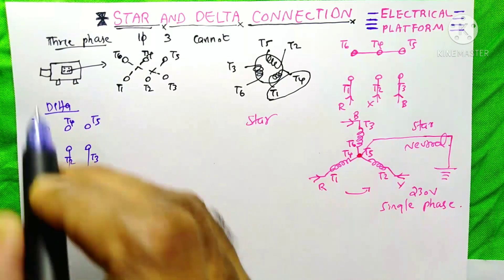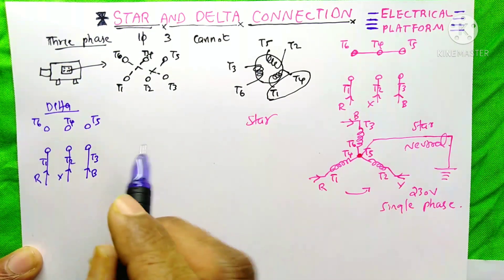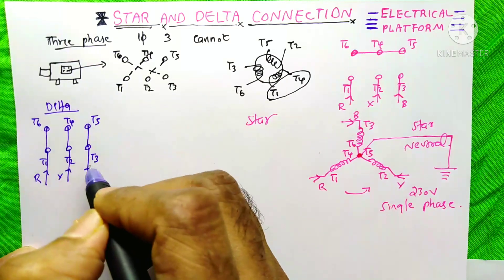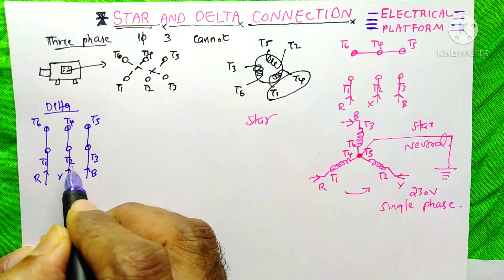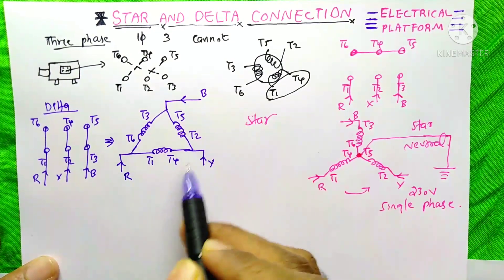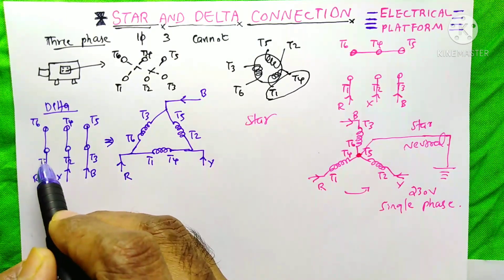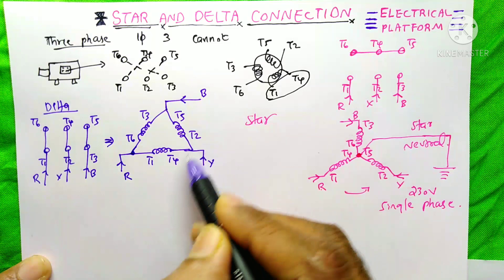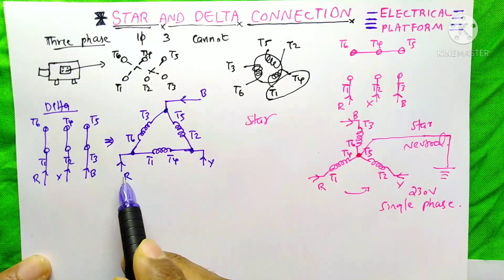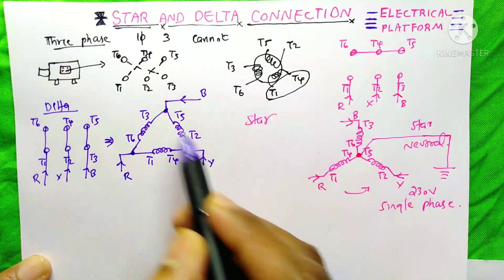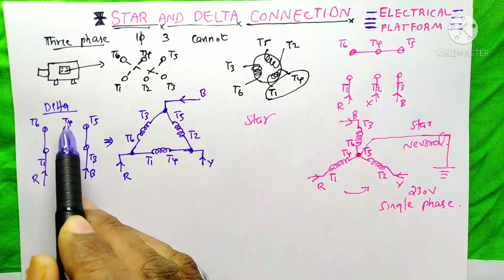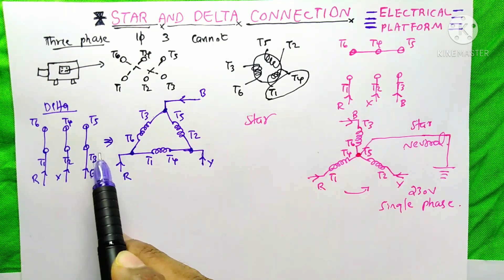Now I am going to show you how to connect this same three-phase motor on delta. Before giving power, we need to short T1-T6, T2-T4, and T3-T5. Then give power through T1, T2, and T3 as R, Y, B — same as star connection. In the winding diagram drawn in delta fashion, T1-T6 is connected, T2-T4 is connected, and T3-T5 is connected. There is no neutral point in delta connection, and it is because T4 starts from the middle that we can make this delta connection.